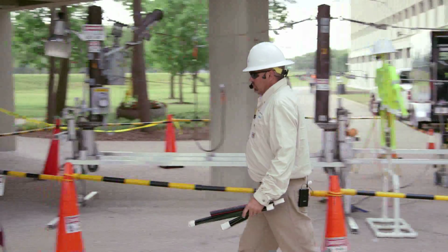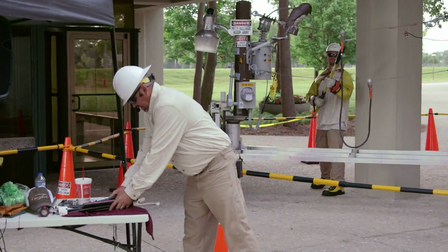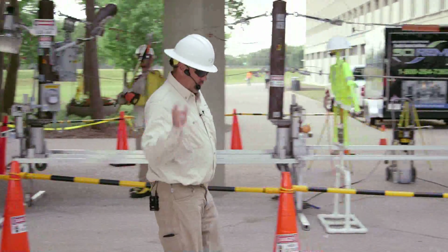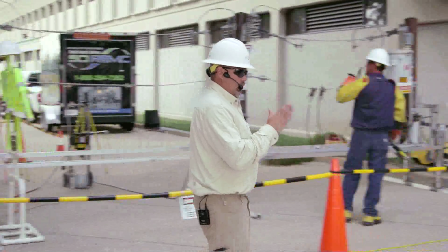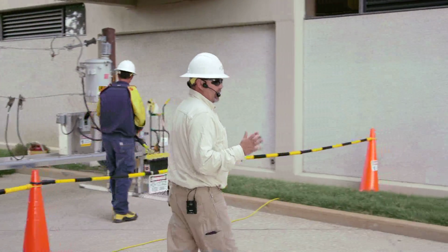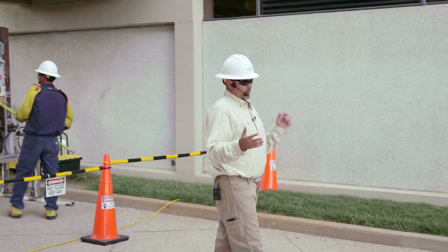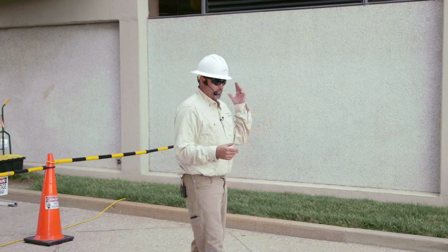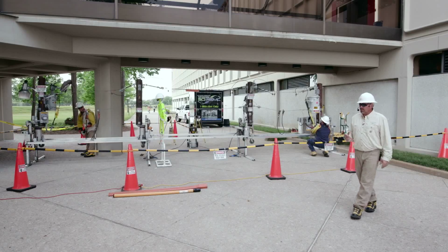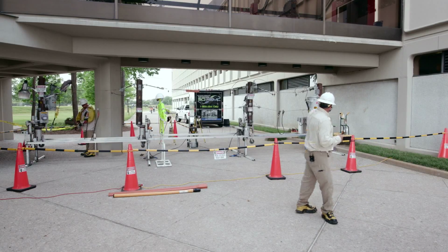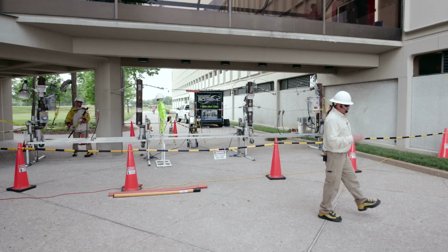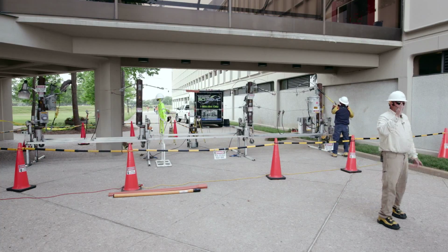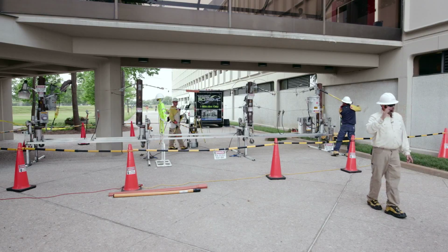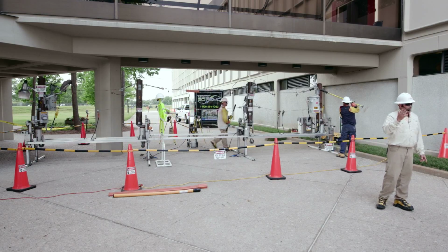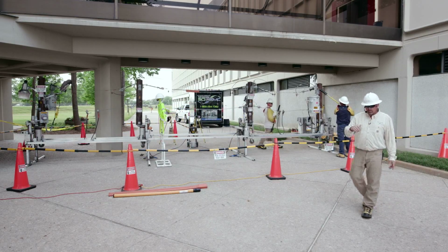We would now have to come out and run pole to pole. We got to go pole to pole to see if we can find the fault, what happened, tree fell, lightning, whatever it might be. Then we would refuse that or reset that breaker. That breaker has a handle, so it's just being reset, kind of similar to the same fashion that your breaker in your house is reset, okay? Very similar to that.